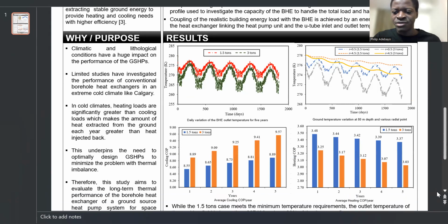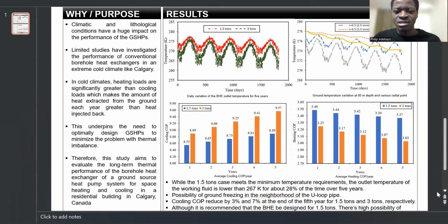So looking at the coefficient of performance during the cooling season, we could see that the 3 tons case has higher cooling performance, while the 1.5 tons case has lower cooling performance. And on the contrary, during heating mode operation, which is majorly during the winter when we need to extract heat from the ground, we have the 1.5 tons load capacity giving us higher COP, coefficient of performance, during the heating operation, and we have the 3 tons case giving us lower coefficient of performance during the heating operation.